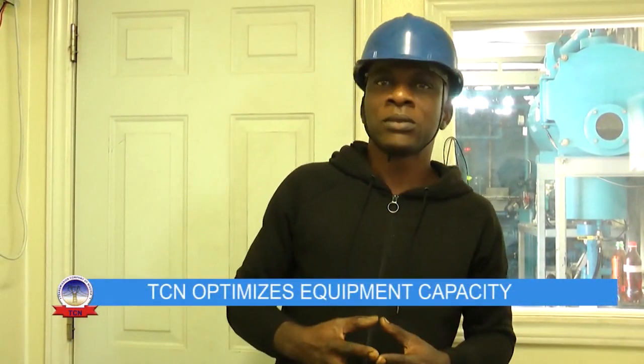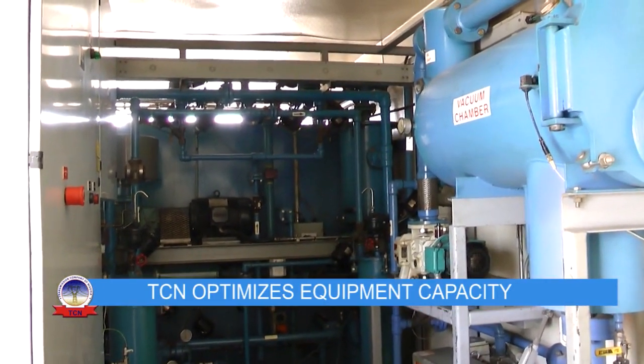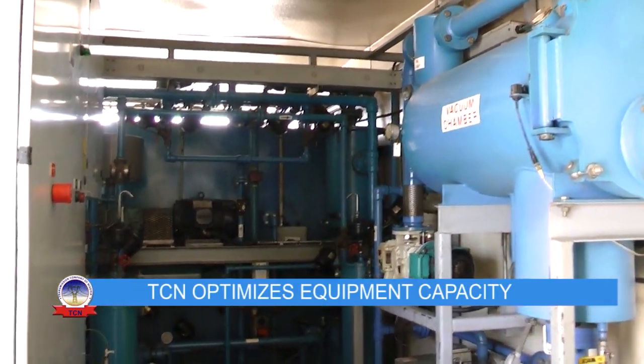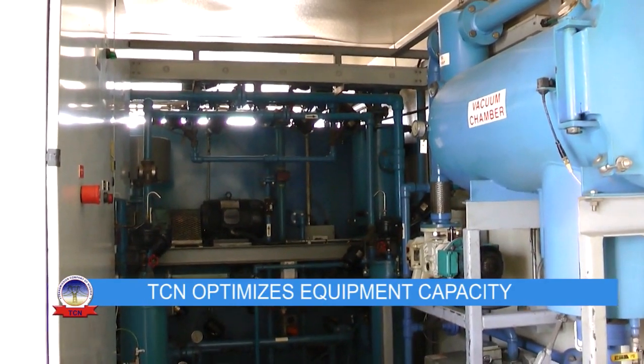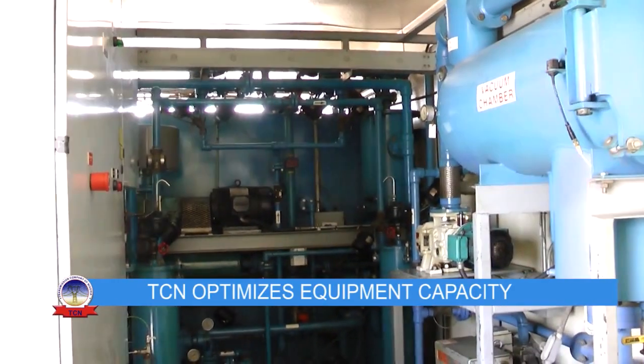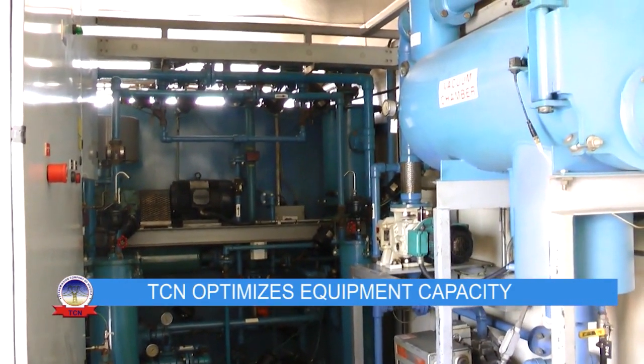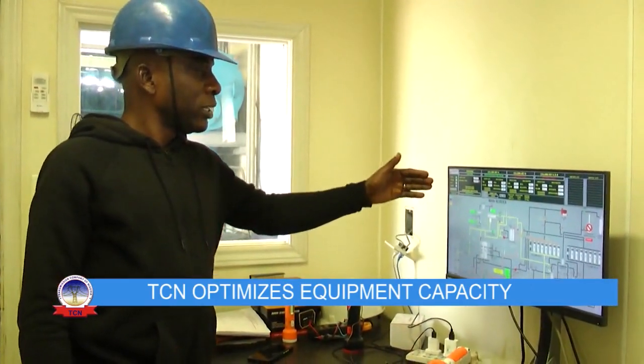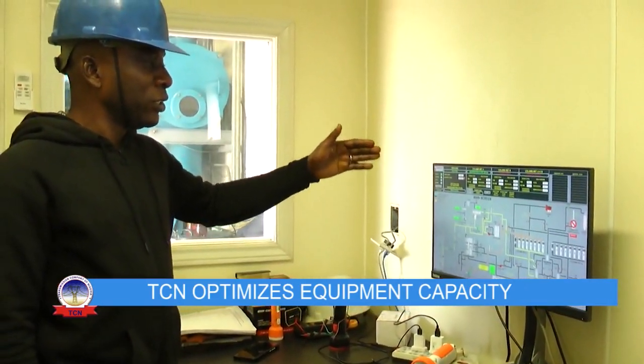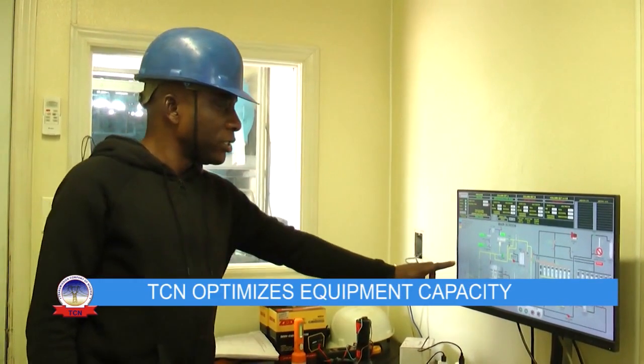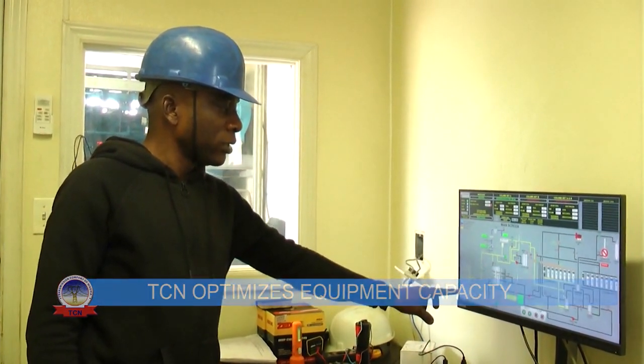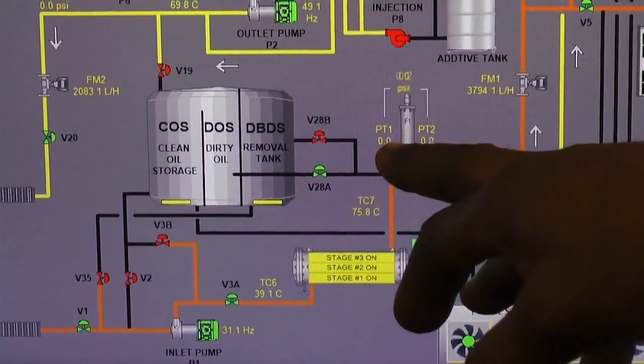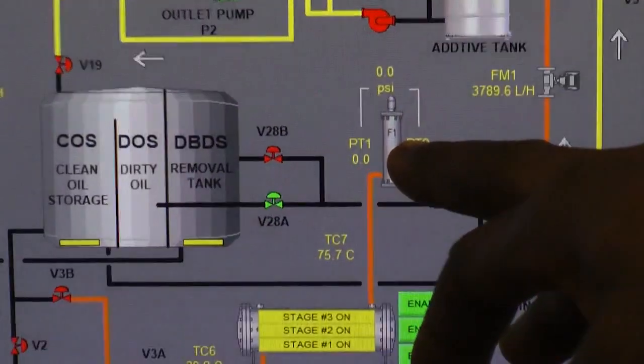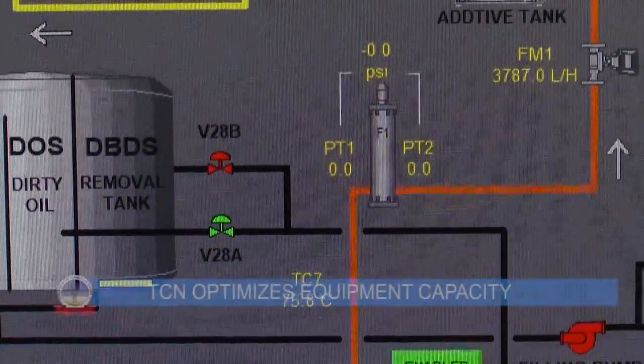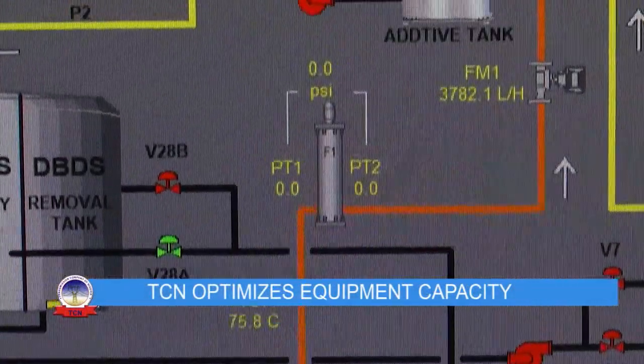While the RSM is connected to the power transformer for the regeneration process, the engineer monitors the process in the control section of the regeneration system vehicle. The screen now shows the process of regeneration on the transformer. You can see this transformer outside here is 90 MVA, and this is the system, the software that controls the machine outside.